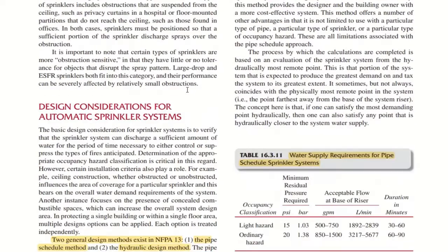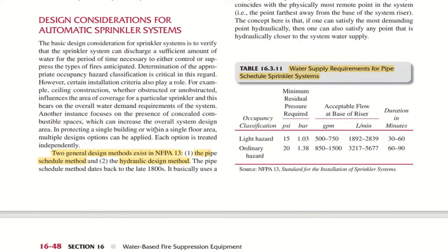So here you have the design considerations for automatic sprinkler systems. Basically there are two design methods existing in NFPA 13: the pipe schedule method and the hydraulically designed method. This is an important point. Water supply requirements for pipe schedule system. This is an important table. You need to go through this as well. Occupancy classification, for example light hazard or ordinary hazard. For light hazard, minimum residual pressure will be 15 psi. For ordinary hazard, minimum residual pressure will be 20 psi, and the acceptable flow at the base of riser will be 500 to 750 gpm for light hazard and 850 to 1500 gpm for ordinary hazard, and the duration for light hazard will be 30 to 60 minutes and for ordinary hazard 60 to 90 minutes.